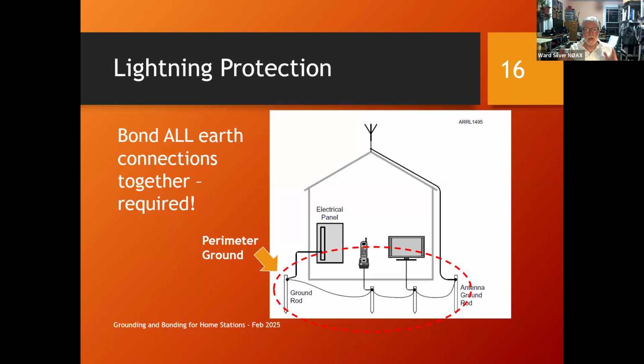The NEC is unequivocal on this. They use the word shall. And if you've ever done any contracting, you know the word shall has no wiggle room. This is the way it's got to be. And the NEC says all external ground electrodes shall be bonded together. And the reason is, if you have a big lightning surge that flows through the earth, and you measure the resistance between those ground rods, you might measure 10 ohms, 20 ohms, 50 ohms, 100 ohms.